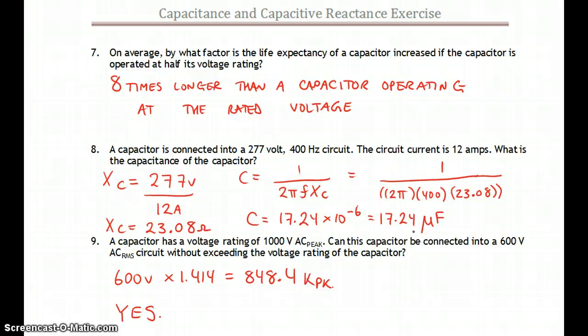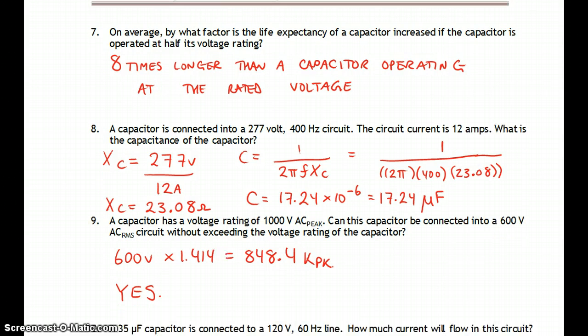Number nine. The capacitor has a voltage rating of 1,000 volts peak. And can you put it into a 600 volt RMS circuit? Well, we know that 600 volts times 1.414 gives the 848 volts peak. So it looks like we're good to go there. We're well within the range of 1,000 volts.